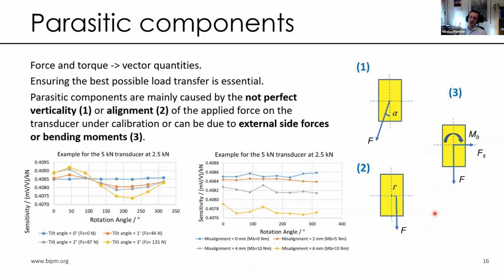In torque, the sources of parasitic components are basically the same. For imperfect verticality, some results can be seen when you rotate a force transducer around its axis and you do not have perfect verticality between the plates, the upper plate and the bottom plate, between which the force transducer is mounted. Then a more or less sinusoidal dependency can be seen for higher angles.